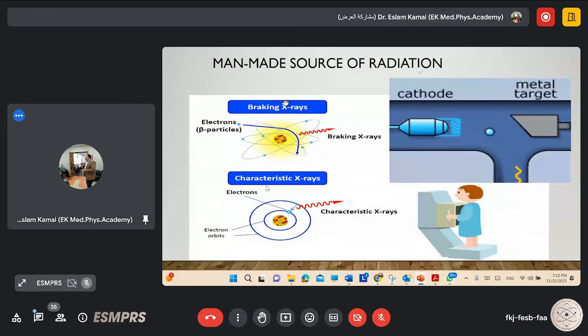This X-ray tube will produce our X-ray based on the interaction happening between the electron coming out from the cathode and the target anode. You are controlling the energy and number of photons produced from the X-ray tube by adjusting the kilovolt or the potential difference between the cathode and anode. When you increase the potential difference, that means you are giving more energy to the electrons to move towards the target anode.